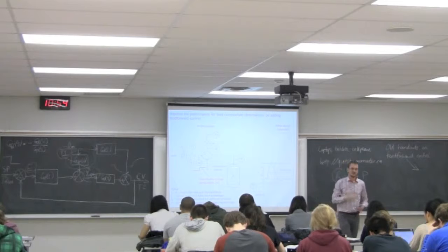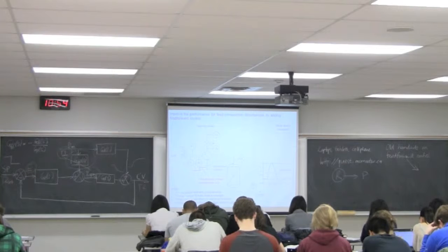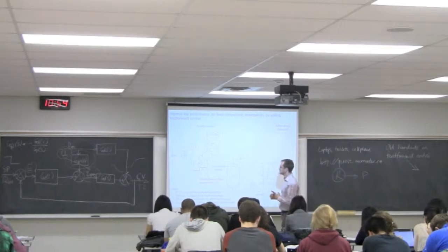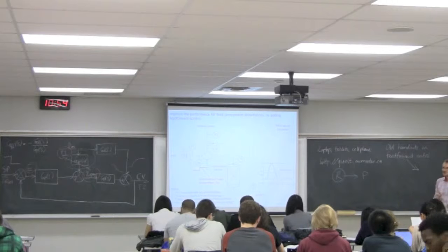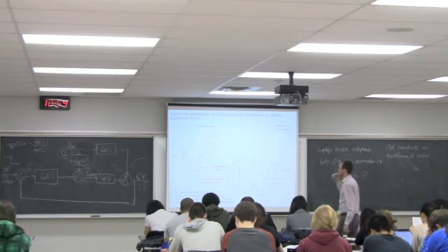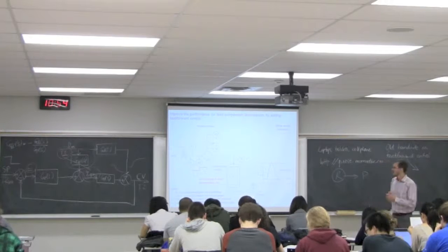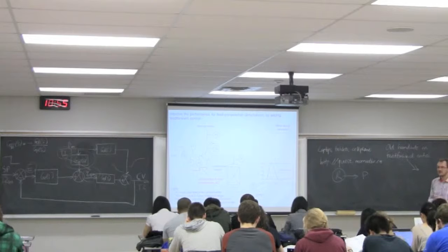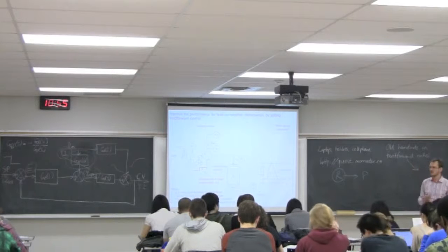Does cascade control work here for that disturbance? What were the requirements for cascade control? The first requirement is that you get poor performance. Let's assume you have poor performance where A2, this inlet concentration, varies. We see an unacceptable deviation above a maximum. So that's checked off. The next requirement for cascade control: A2 is measured. Okay, that's true, it's measured. What's the next requirement? That measurement indicates the presence of the disturbance we're considering. Does that work? Yeah.